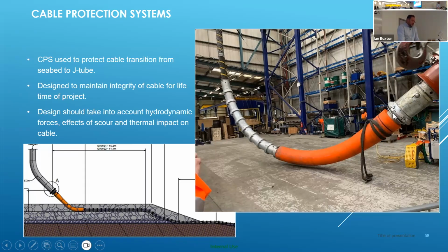You pull the cable protection system into this bell mouth, and it locks in place in this instance with this ball and taper technology, which is a patented technology from this supplier. It then has a flexible PU bend limiter, which stops the cable bending or over bending, and then these what are called steel half shells, which basically act as ballast to maintain the cable's position on the seabed and stop it getting affected by the hydrodynamic forces offshore.